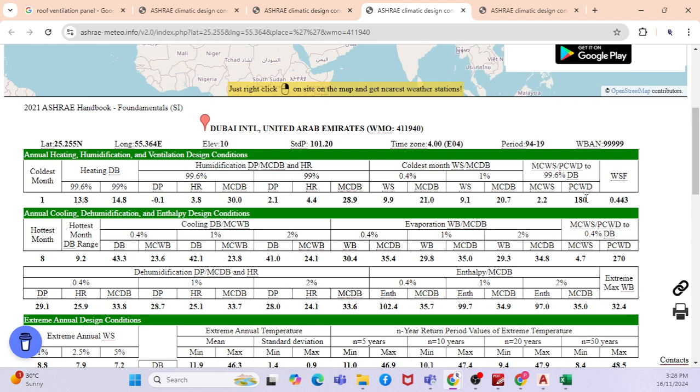So what they will do is locate the generator room in such a way that the fume will be discharged to the outside, not towards the building. That is the way they decide, based on what you normally hear about as CFD analysis. The fumes will be very high temperature and may affect the nearest chiller plant room, so that study they will do based on these particular values.